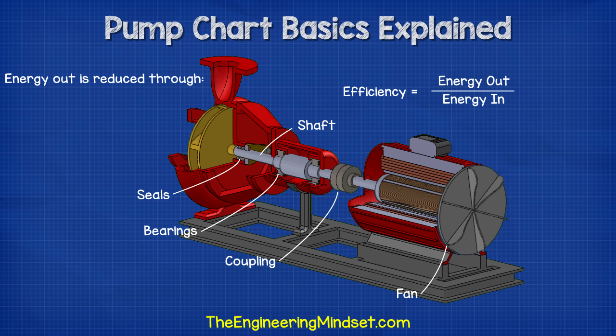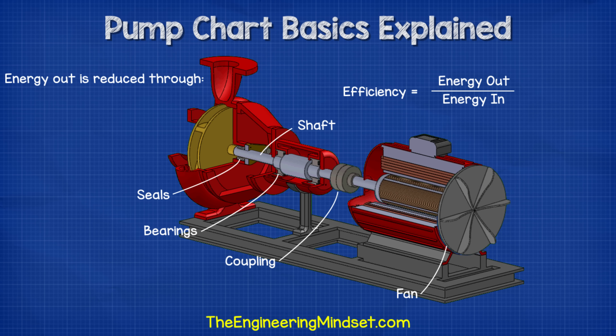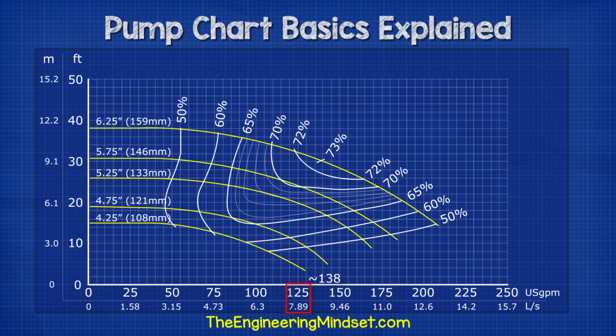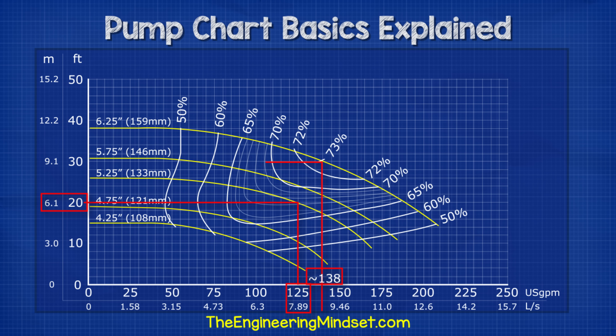The pump will always lose some power when it converts and transmits electrical energy into mechanical energy, and this will be lost through the couplings, the bearings, the shaft, the seals, the cooling fan, etc. For example, on this chart, we can see that if the pump provided 125 gallons per minute at 20 feet of head, then it would run at around 67% efficiency, which isn't very good. If the same pump operated at 30 feet of head for 138 gallons per minute, then it would operate at its peak performance of 73%, which is much better.